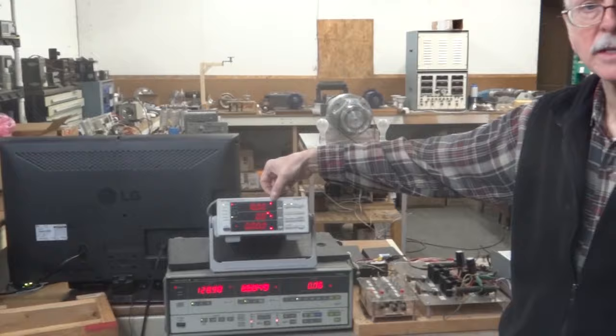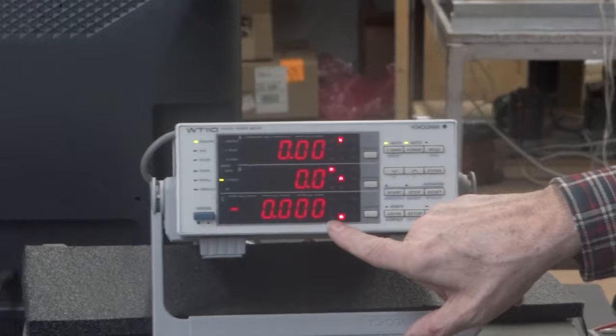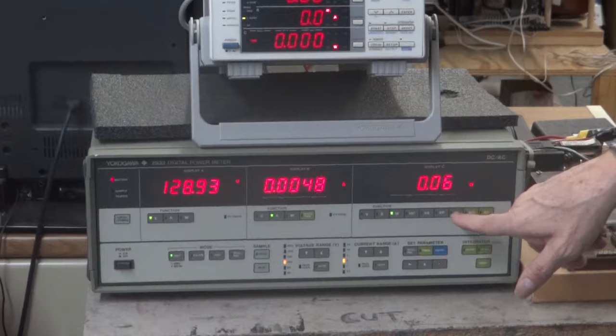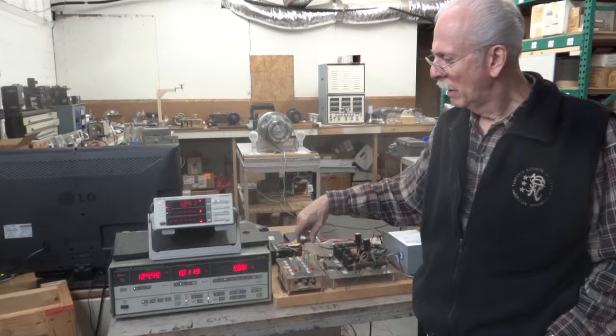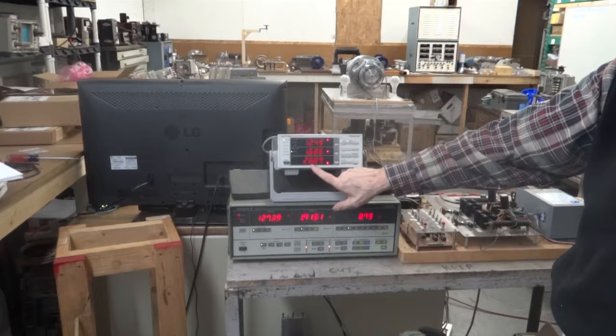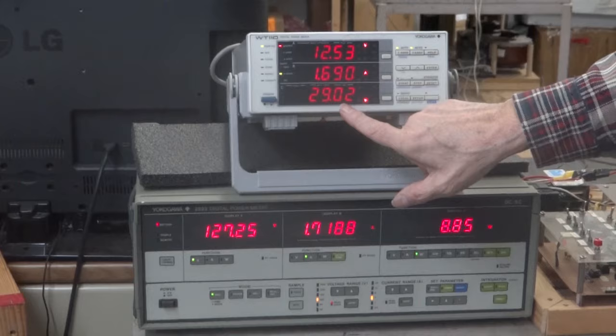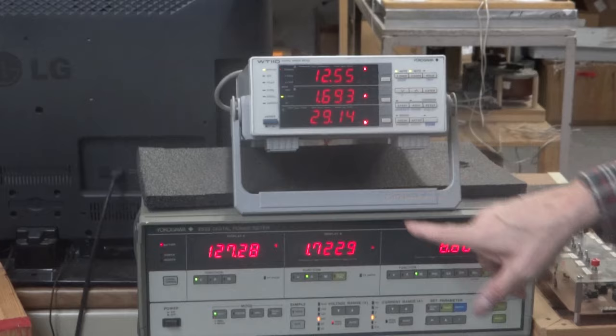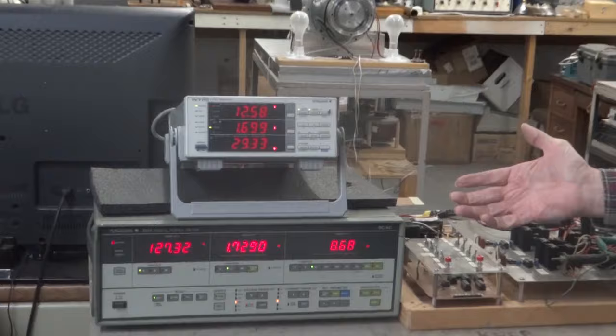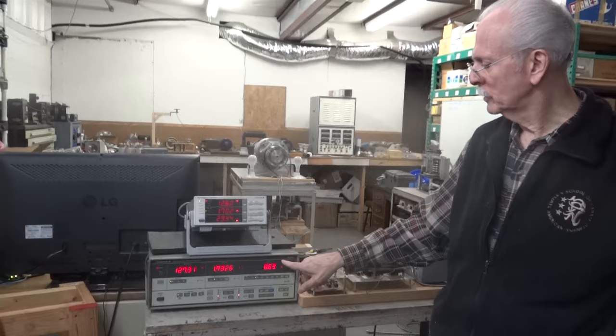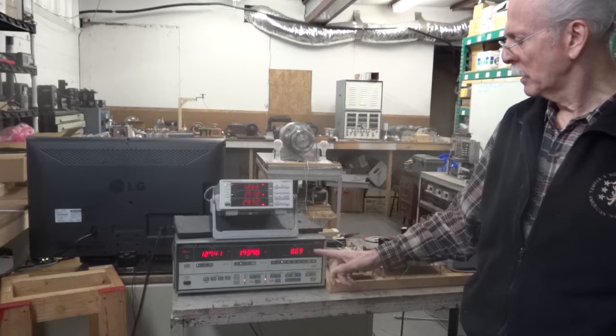This is going to be the voltage reading on the top. The second one is going to be the amperage. And the bottom one is going to be the wattage. Down here, it's going to display volts, amps, and watts. But I have the option of looking at other parameters. And I will do that once we get this device turned on. So with that preliminary information, I'll switch on the processor. And hopefully, we'll get some interesting numbers. So now you can see that we are pulling or dissipating in that resistance 28.92 or 91 watts. But the actual reading that the line sees is only 8.77 watts. And that's not because we're creating any power. It's because of the fact that when you return power, you get a different effect.